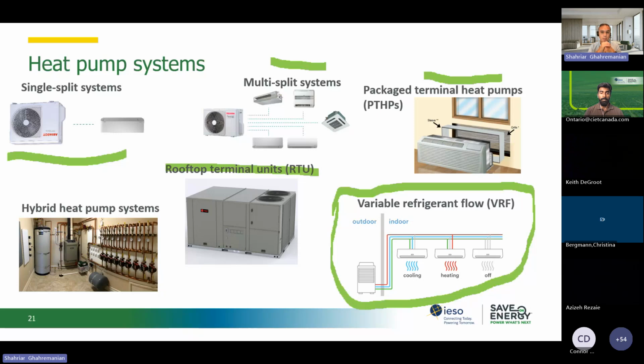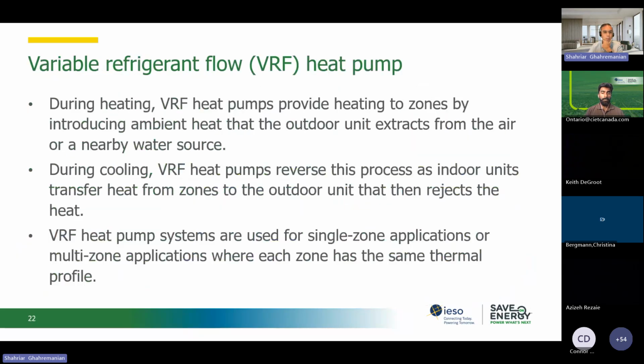So that's a VRF. I will speak a little bit about the VRF in more detail, similar to water source heat pumps. A VRF, variable refrigerant flow, is a heat pump, and it can provide heating or cooling to different zones by piping the refrigerant to those zones and then installing a system like a fan coil or ceiling beams to heat up or cool down those areas. The VRF system is best used for multi-zone applications, and it can handle different thermal profiles as well. One wants super hot, the other wants a super cool environment. VRF can accommodate that. And again, the main concept is transferring the heat from one place to another. In the summer season, that means from inside the building to outside. In the winter season, from outside to inside.